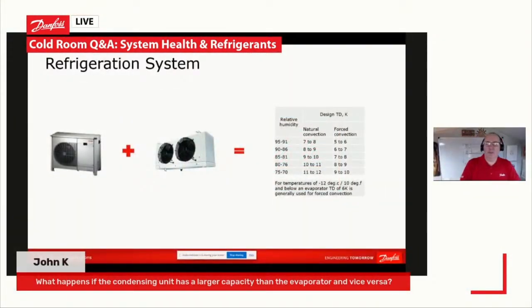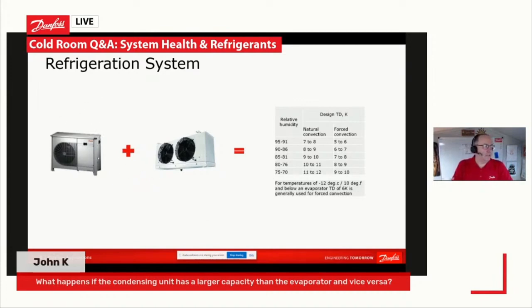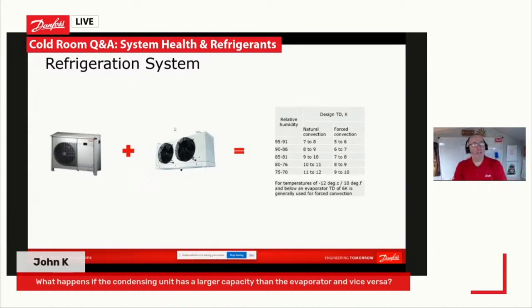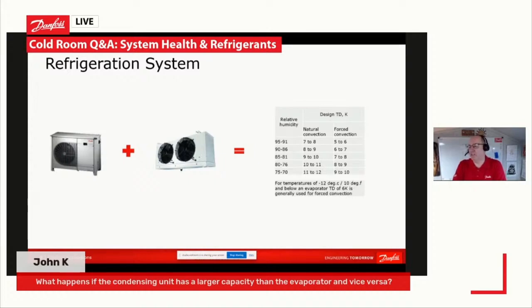So if we think of a nice simple cold room refrigeration system, we've got our condensing unit, our cooler, and the match between those two. Let's say that's 10 kilowatt and that's 10 kilowatt — that's matched. At that match, we'll have a particular temperature difference, and that will give us our humidity on our cold room. We've got our design TD, our temperature difference between evaporating and air onto the cooler at a specific delta T.